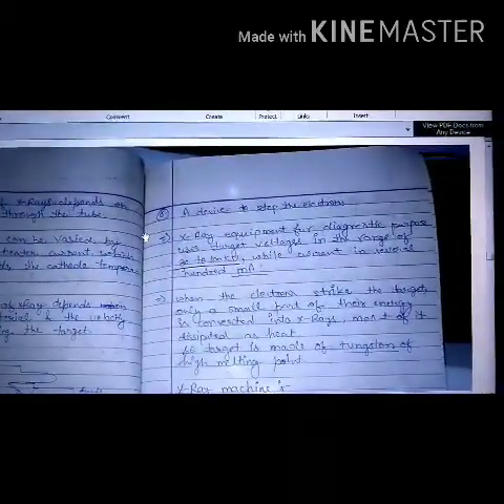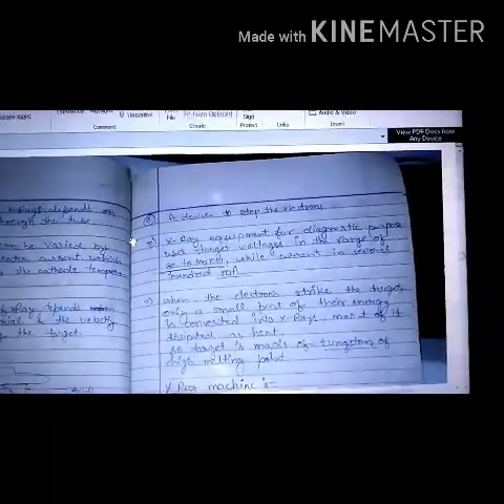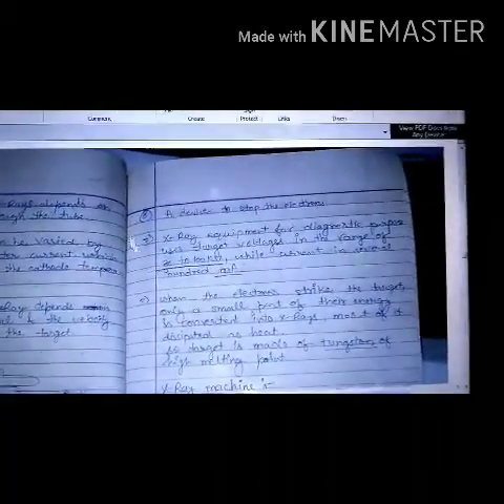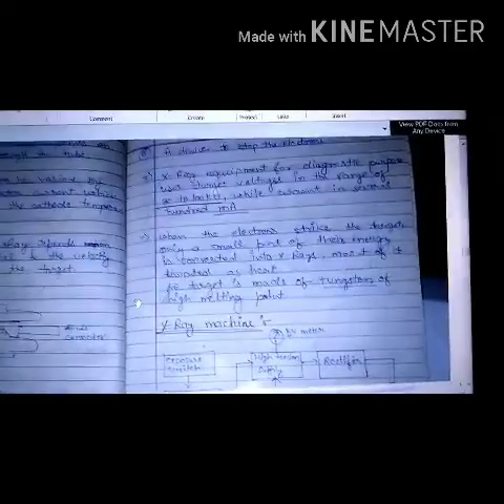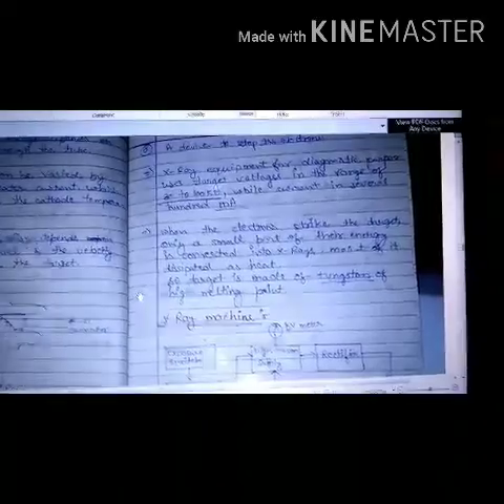When the electrons hit the target, only a small part of their energy is converted into X-rays, and most of it is dissipated as heat. So it is not a very efficient device. The target is made of tungsten, which has a high melting point and does not melt easily when the electron beam hits it.